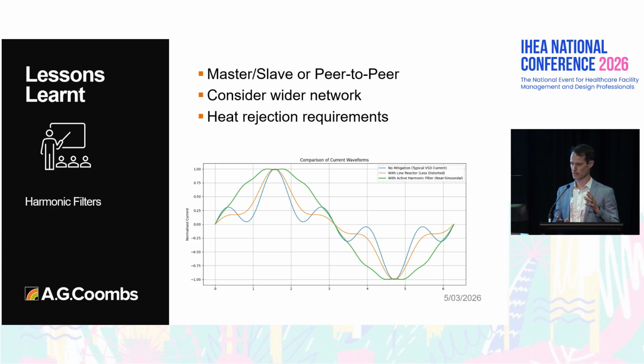I guess the other thing, I'm a big advocate of putting the harmonic filters on the mechanical switchboards as opposed to what typically gets done around specifying chillers with harmonic filters. In most cases, when it gets specified with an active filter, it'll get value engineered off and they'll put a line reactor or something in. They don't really serve the same purpose. The line reactor is to protect the VSD. The harmonic filter is to look after the network.